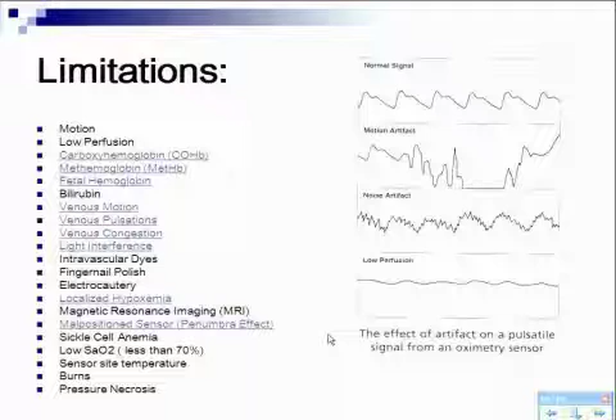The new pulse oximeters have a new algorithm that basically avoids that problem. But if you work in a place that hasn't replaced their pulse oximeters in the last, say, 8 years, you might still have that problem. And the way you solve it is really easy. You just put a blue towel on your hand, and that's it. This has got to include the air and light. The other things that give you true desaturations are carboxyhemoglobin, methemoglobin, and fetal hemoglobin. Okay, bilirubin can also, when it's very, very elevated. I've never seen that being too much of a factor most of the time. Jaundice, though, to very severe degrees, can cause the pigmentation, but doesn't really give you a true desaturation. But the pulse oximeter will give you an abnormal value. If you have light interference, which I just talked about, intravascular dyes, which I just talked to you about, fingernail polish, especially in the blues and blacks, electrocautery, which is a big problem.